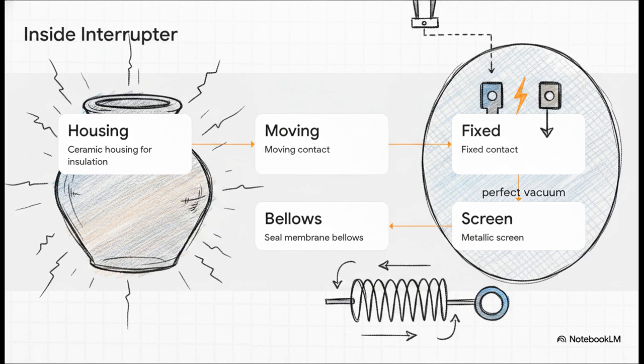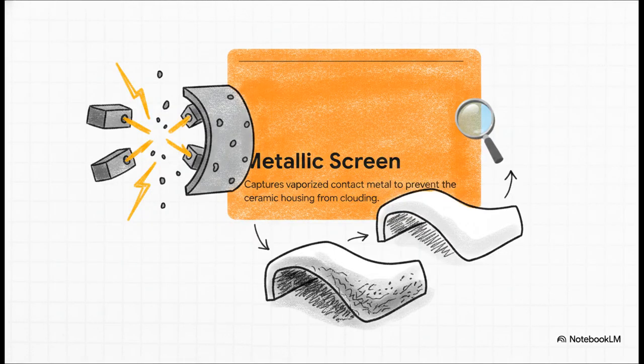Inside that, the actual electrical connection happens between a fixed and a moving contact, all suspended in a perfect vacuum. Around them sits a metallic screen. And finally, down at the base, a seal membrane bellows allows that moving contact to physically travel up and down, making and breaking the circuit, all while perfectly maintaining that vacuum seal. It's an elegant setup. And this brilliantly solves a massive physics problem.